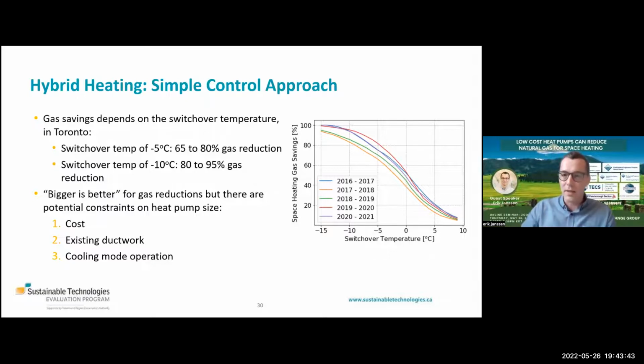This is some of our analysis at -5. If we can switch to air source heat pump above that value, based on previous years' data, we're in 65 to 80% gas reduction. If we can get down to -10, we're in the realm of 80 to 95%. So if we can get a switchover temperature between -5 and -10, we're really doing the lion's share of the heating of the home with a relatively lower cost air source heat pump.